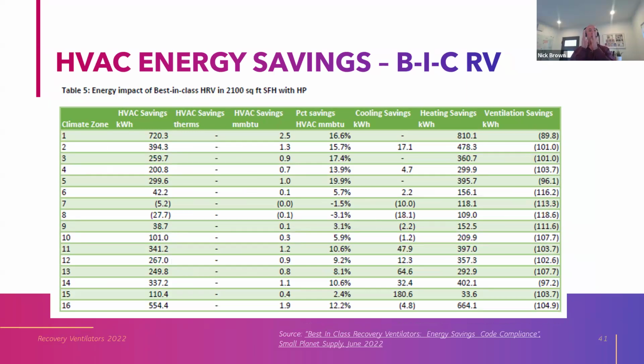The ventilation penalty is less, the heating and cooling savings is more, and so you've wiped out all the negatives except for 7 and 8 in the HVAC savings kWh column, and you've increased the magnitude of the savings. As a percentage, those savings in 1 through 5 are 16, 15%, right? Pretty solid. But they're a lot smaller in 7 and 8 and 9, the more moderate climate zones.